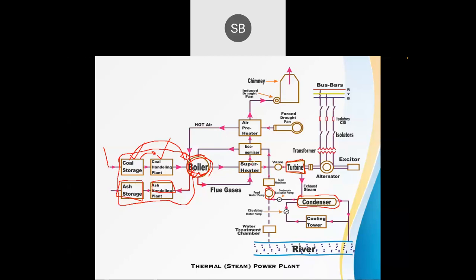Whatever exhaust waste energy remains is again utilized in the superheater. Then it is passed through the economizer. The economizer increases the feed water temperature. Whatever water is given to the boiler, we first increase its temperature from atmospheric temperature to a higher temperature, so less fuel is required inside the boiler. So the flue gases first pass through the superheater.